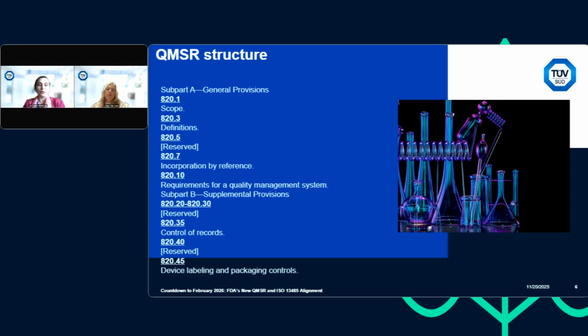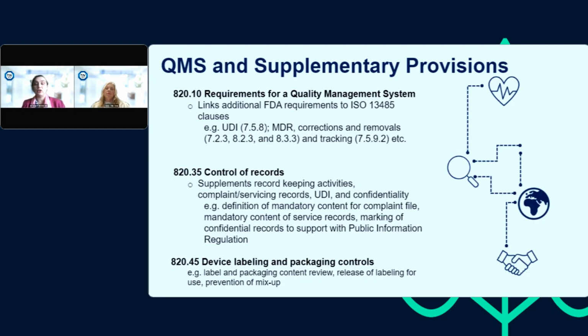Now, in addition to ISO 13485, we have those additional requirements that already existed within the quality systems regulation and are not explicitly documented in 13485. Those supplementary provision sections have been embedded specifically within the regulation itself. And then you have 820.35 talking about control of records, and 820.45 talking about device labeling and packaging control. Those would be defined and documented within the final rule. We have a couple of examples of those additional supplementary provisions just to help gauge a little better where we currently stand with that.